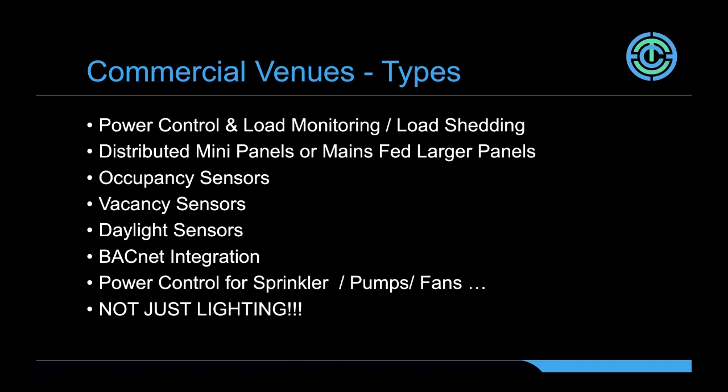So we'll talk quickly about load shedding. California has this mainly. It doesn't happen a lot in Ontario and Quebec yet. Vancouver is starting. But load shedding is a demand response environment where the service provider or even facilities provider can provide information to the power control system or lighting control system that says, hey, we're in a high demand rate right now. We need you guys to shed all non-essential loads. So it's the social distancing of power controls.